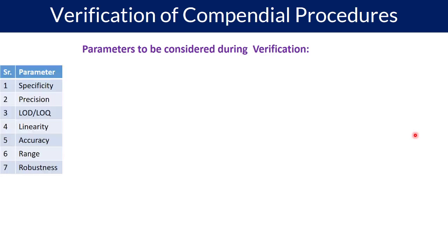Let us now understand what parameters need to be considered during verification of a compendial procedure. There are seven parameters generally considered: specificity; precision — which includes repeatability and intermediate precision or reproducibility; LOD (limit of detection); LOQ (limit of quantitation); linearity; accuracy; range; and robustness.